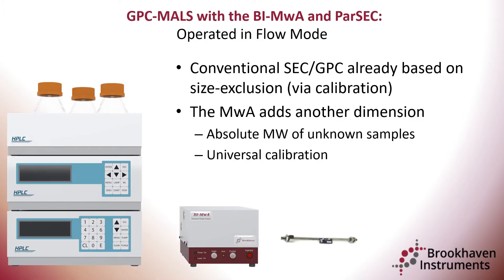Samples are injected onto a GPC column where typical injector loop volumes are between 50 and 200 microliters. The sample plug is pumped through the column and then out through a series of detectors, and finally is either sent to waste or to a fraction collector.